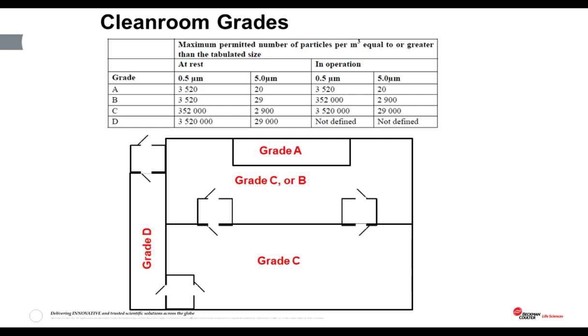People are the biggest source of contamination in the clean room environment. Workers in clean rooms have to pass through several different classes of clean room to enter the production suite. Each area is separated by an airlock, which minimizes the flow of air from the dirtier outer rooms into the clean production areas. Particle counters also have to be sanitized as they move through each grade of clean room, typically done by spraying them with an industrial alcohol called IPA.